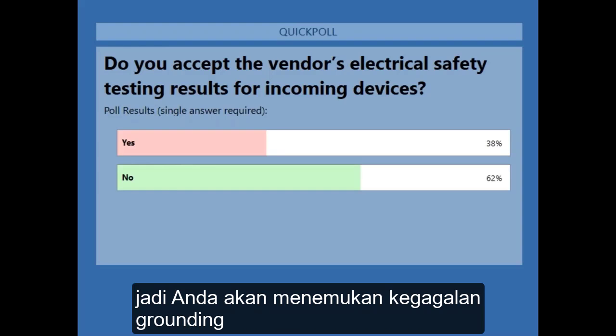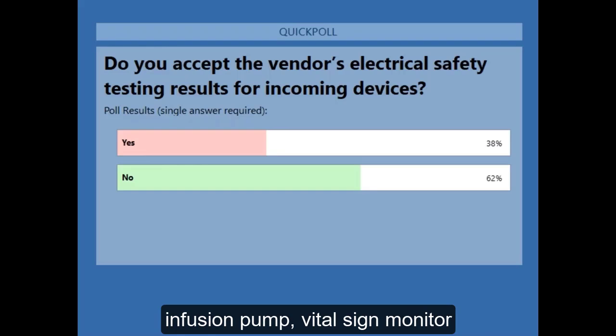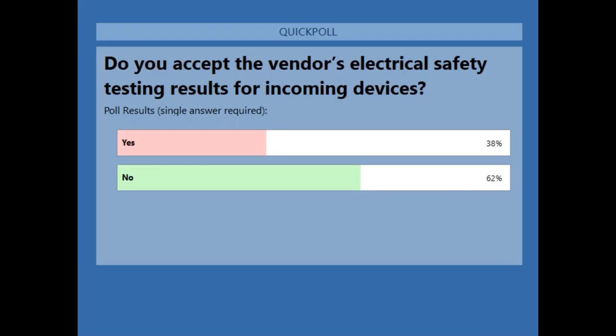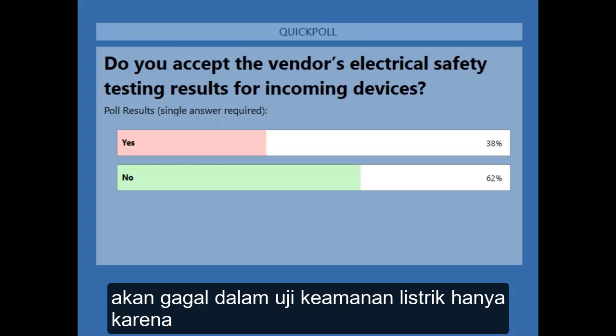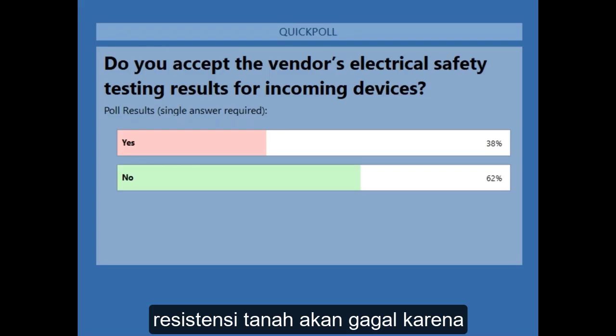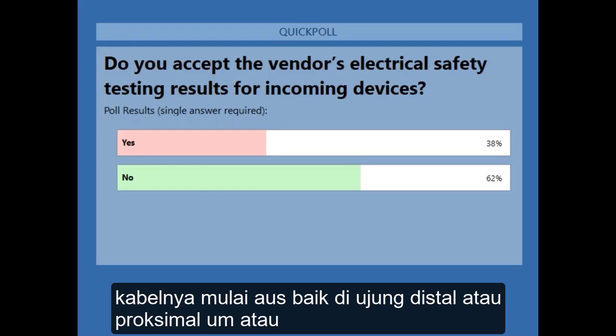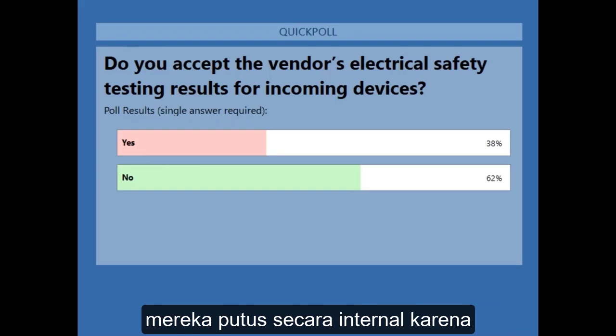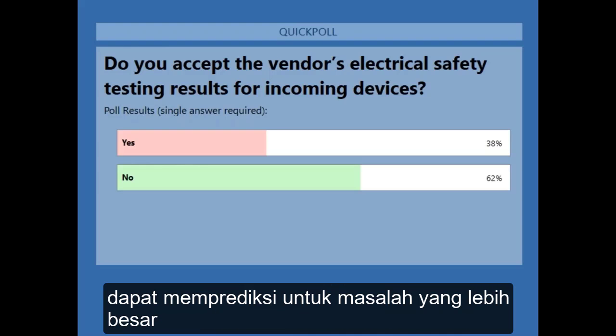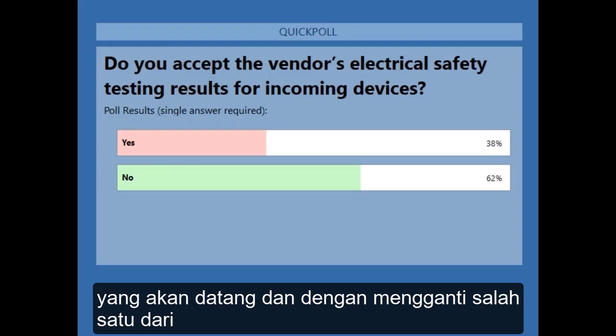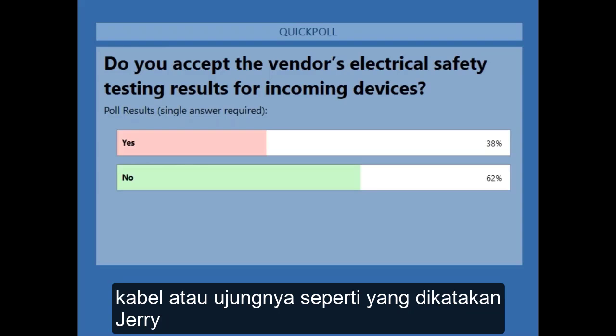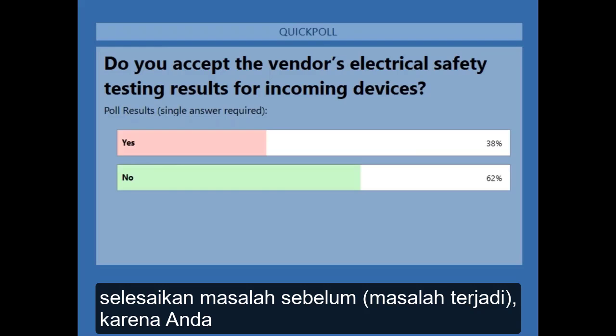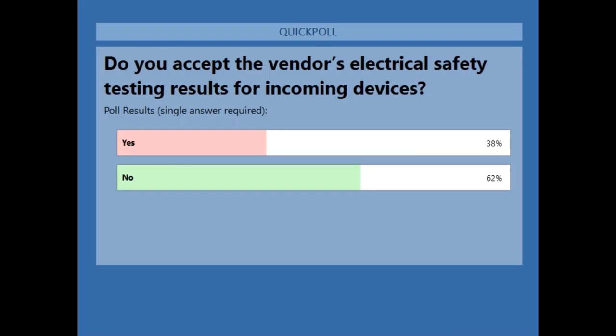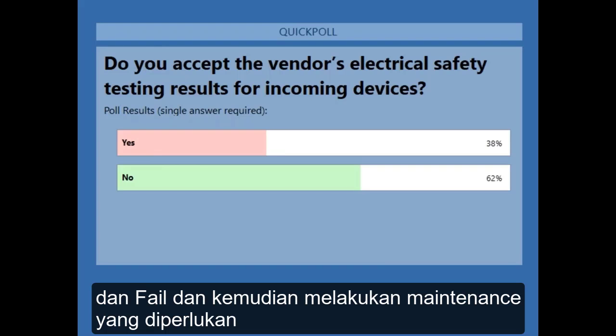So you would find grounding failures - infusion pumps, vital signs monitors would fail the electrical safety test simply because the ground resistance would fail, because the cords were getting worn on either the distal or proximal end, or breaking internally. So doing that test was predictive of a bigger problem coming up, and by replacing either the cords or the ends, like Jerry was saying, you solve problems ahead of time, because you were doing the electrical safety tests, failing them, and then doing the maintenance required.